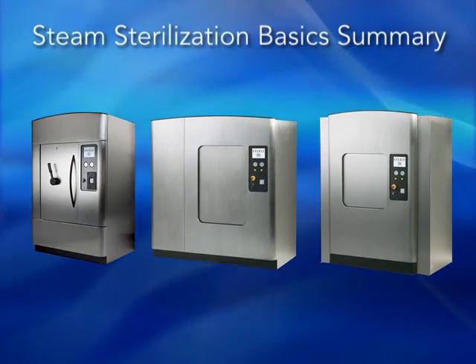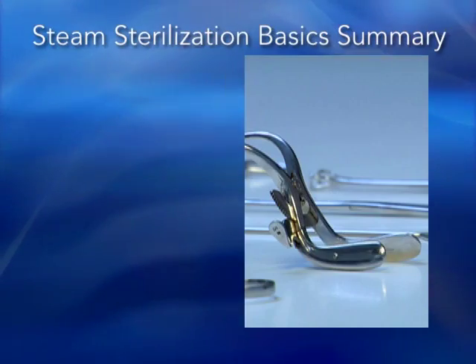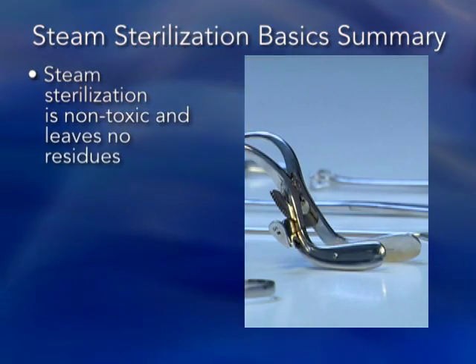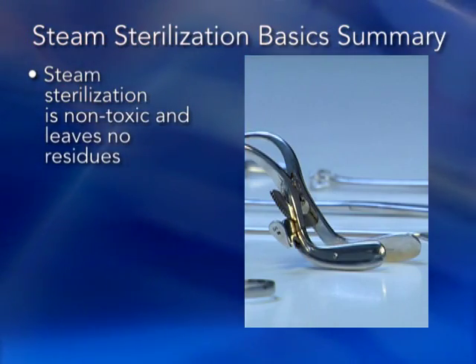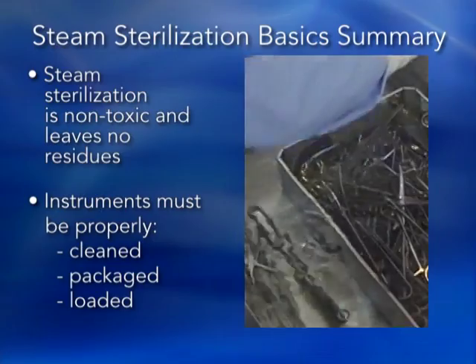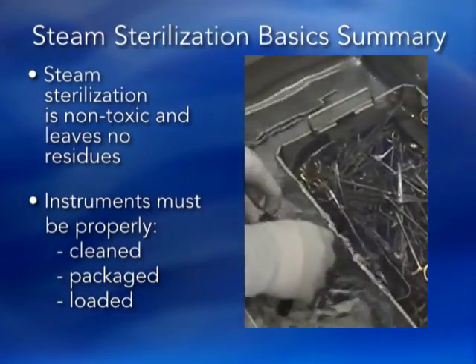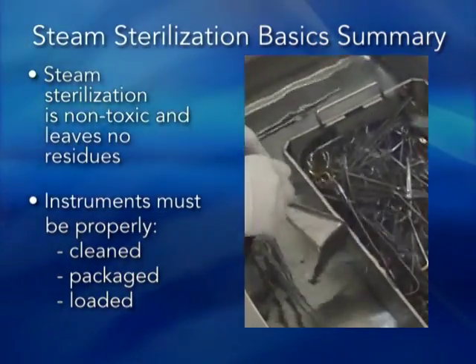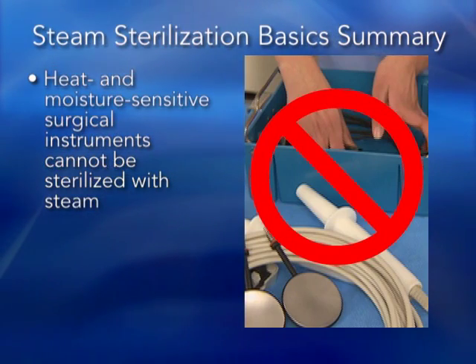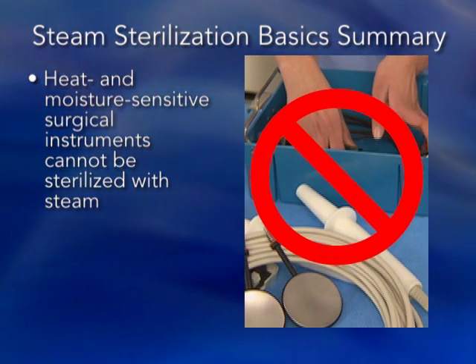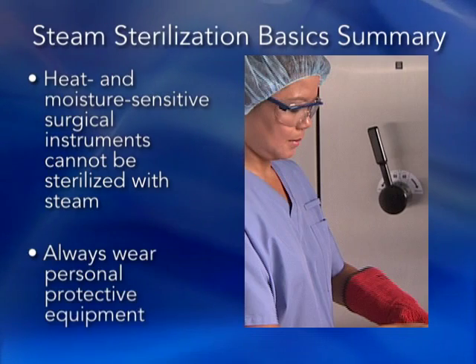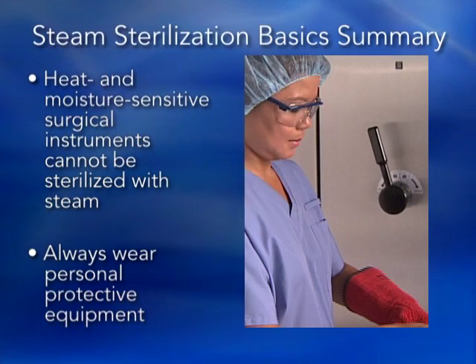Let's review what we've learned in this segment. When used as a sterilant, steam sterilization is non-toxic and does not leave a residue. Surgical instruments must be properly cleaned, packaged, and loaded to achieve optimal sterilization. Surgical instruments that are heat and moisture sensitive cannot be sterilized with steam. Always wear your personal protective equipment.